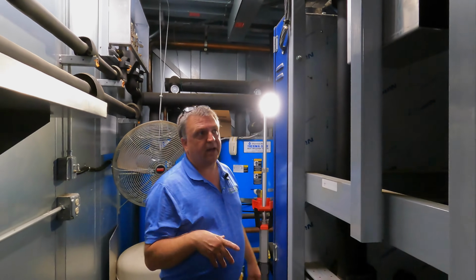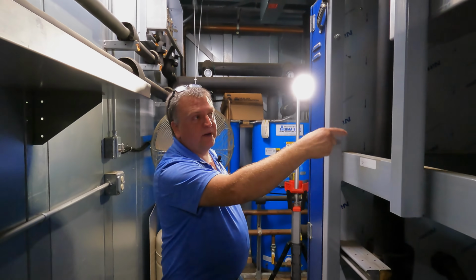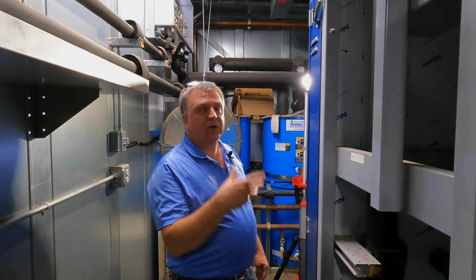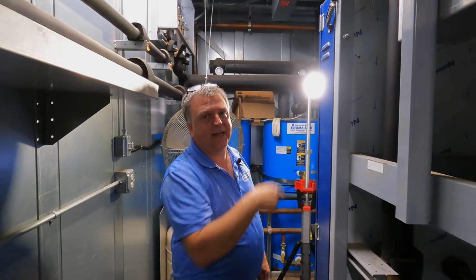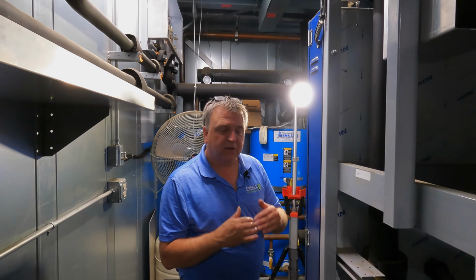Now, the auxiliary condenser is doing the same thing that the rack's doing, just at a much smaller scale. It's just pulling high pressure vapor off the top of the vessel, cooling it down and putting it back into the vessel so we can maintain our pressure under 500 pounds. So when we're doing general maintenance in the store, we always make sure that that thing's working because we don't want it to fail. Let's go outside and I'll show you.